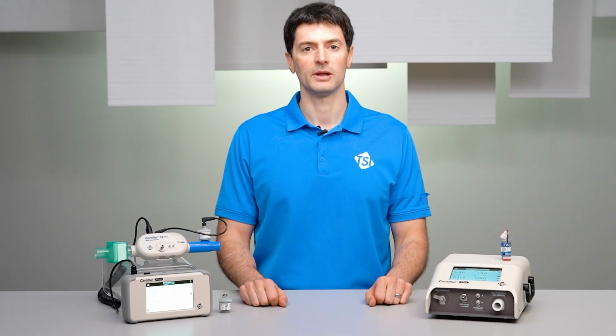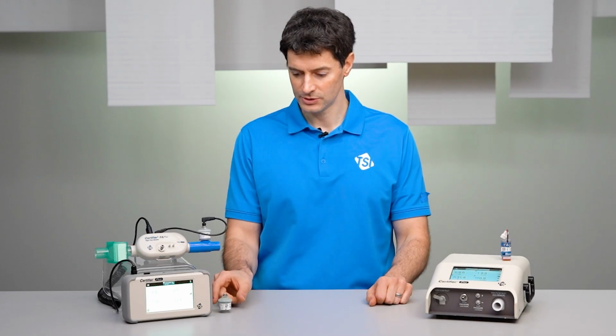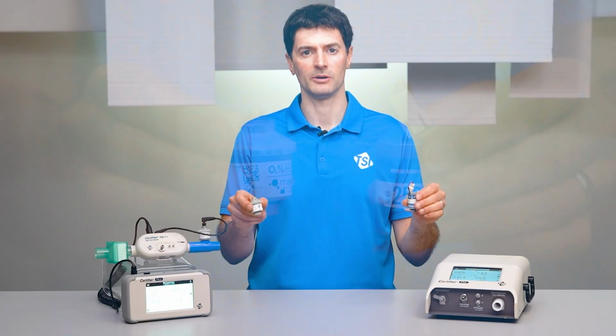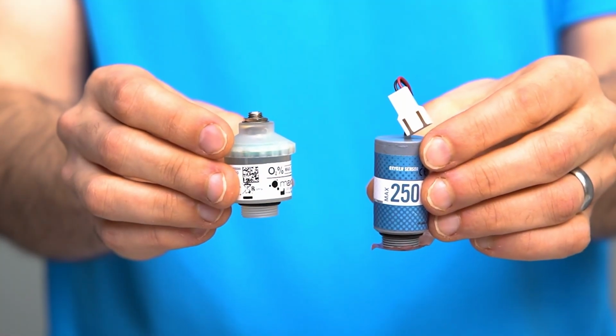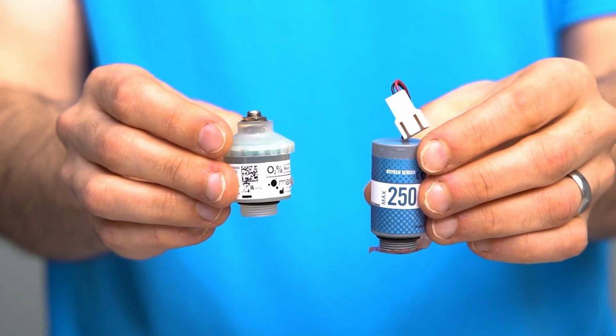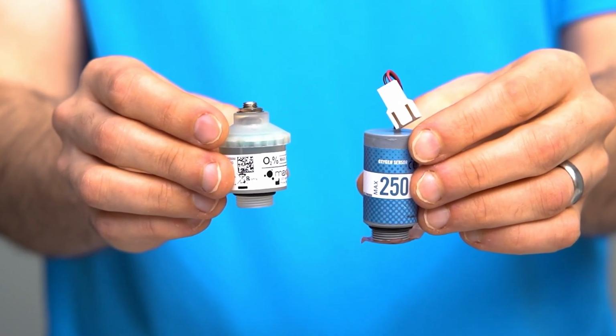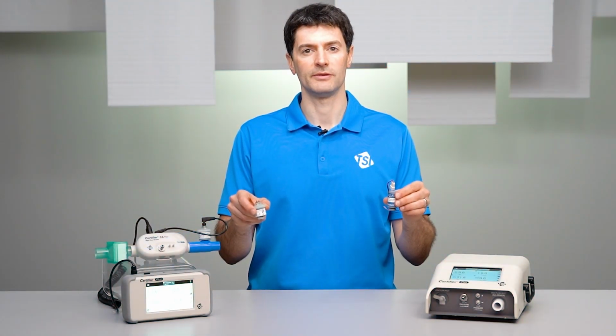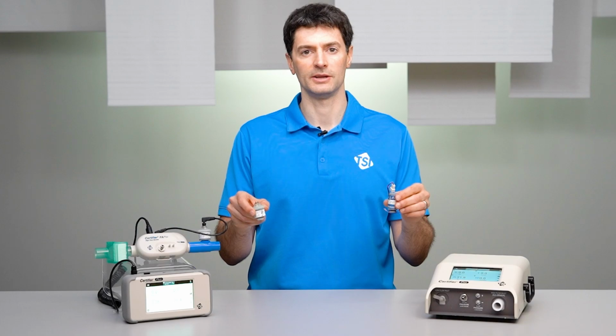The Certifier Plus and Certifier Pro use different oxygen sensor models. However, both sensors are electrochemical type sensors that measure with an accuracy of 2% of reading and have an operating life of 1 to 2 years, depending on their usage.